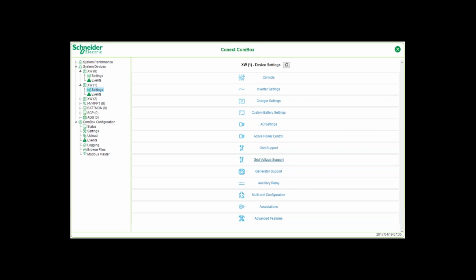Generator support, in case you have a generator that needs some help from the batteries from time to time. And the auxiliary relay has many parameters that you can program to trigger an external device. It also works with state of charge percentage if you have the battery monitor. Multi-unit configuration when you're configuring multiple units. Associations in case you have multiple battery banks or loads.